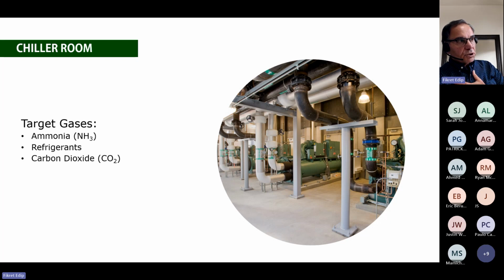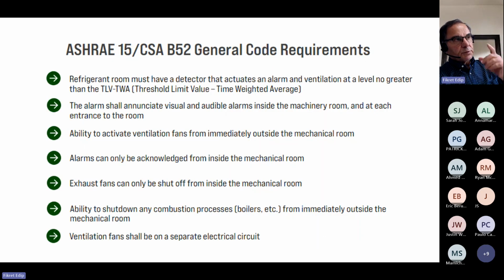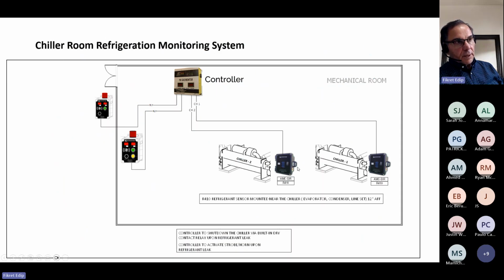In a chiller room application, ammonia, refrigerant, and carbon dioxide are also being used. One thing is important: I put on the screen for chiller room applications the ASHRAE 15 and CSA B52 code, which says here that an alarm can only be acknowledged from inside the mechanical room. I put a quick diagram for you here. You have a controller. You notice I said each chiller will take a sensor regardless of the size of the room, and you put one strobe horn in and one strobe horn out.